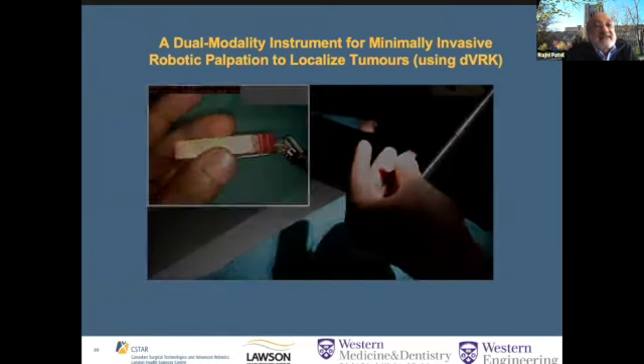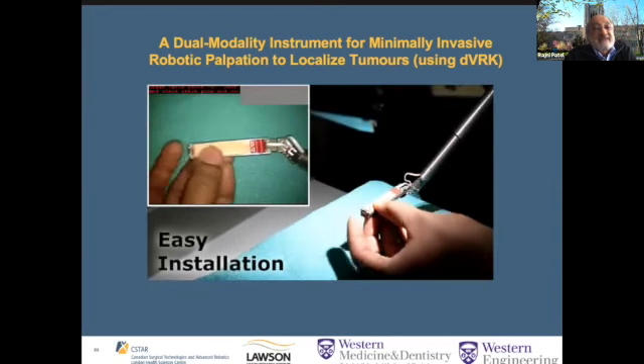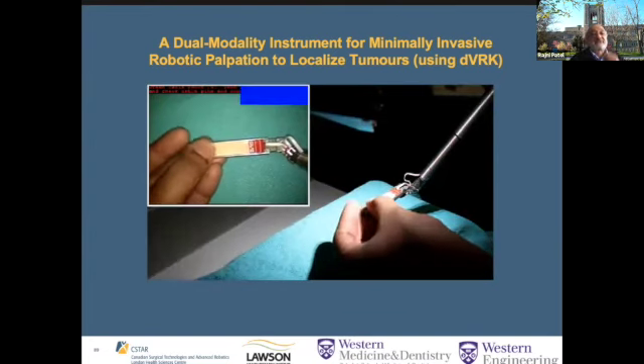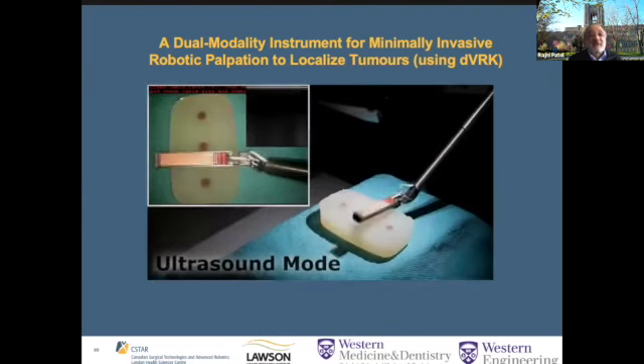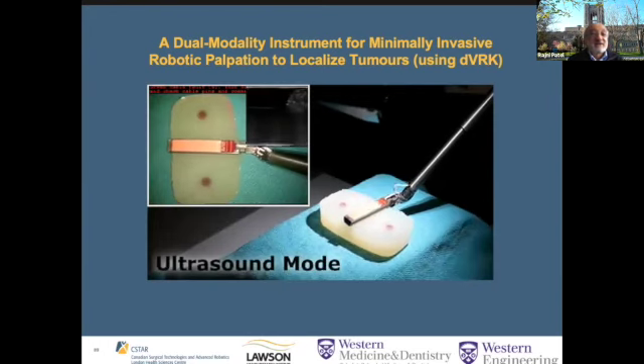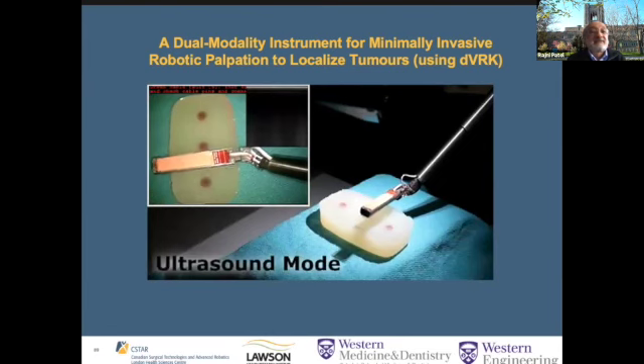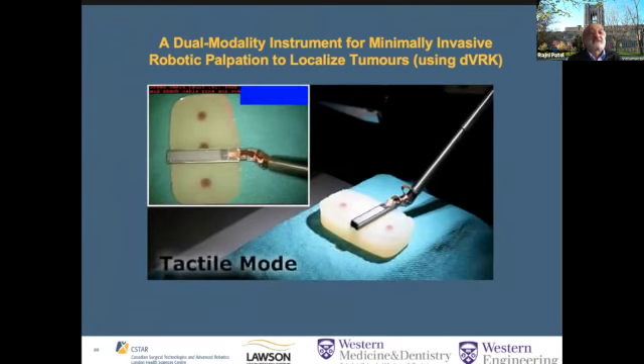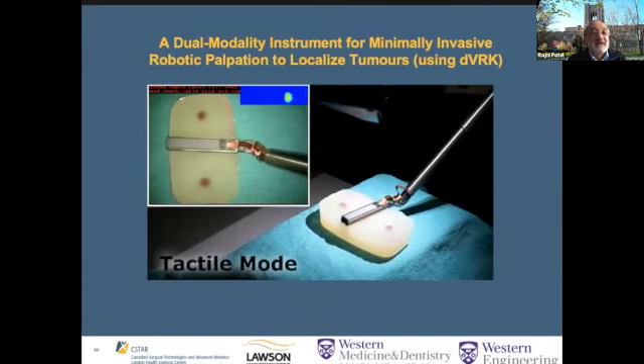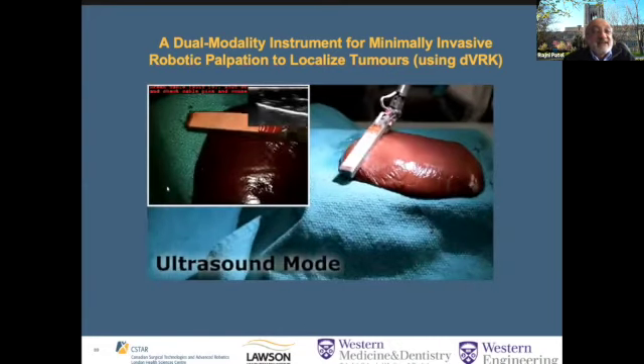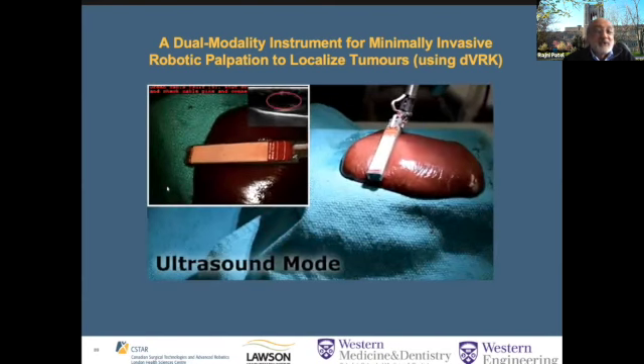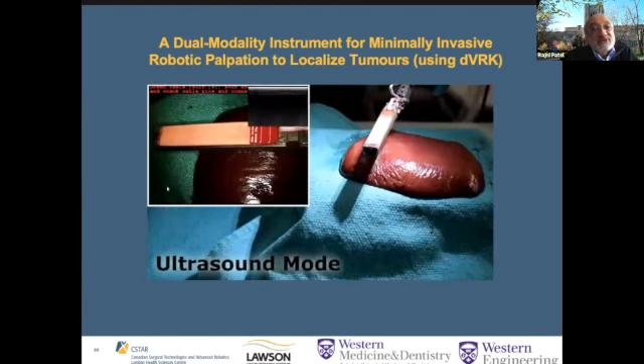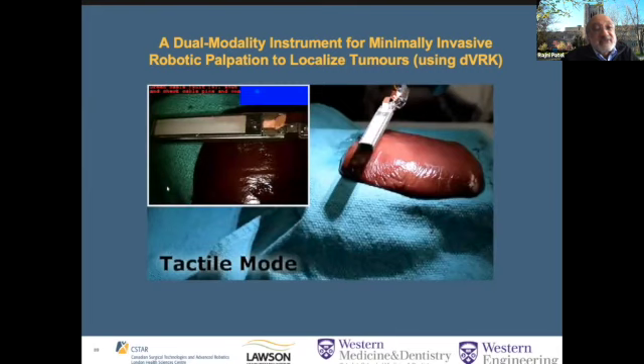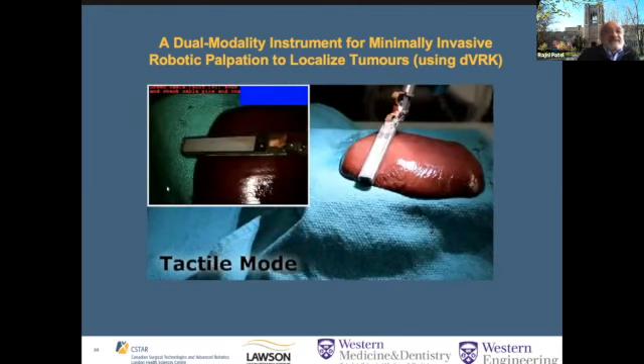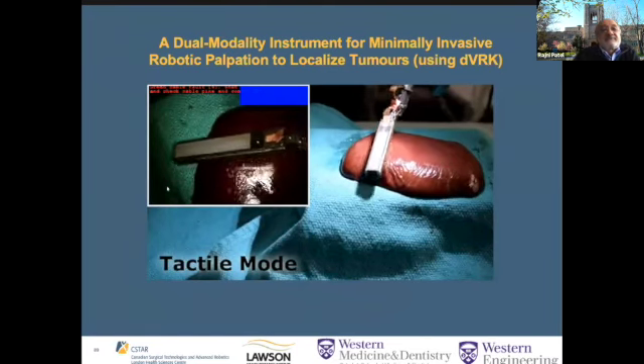So this is the tactile sensor. It can be very easily mounted on the instrument. And on the other side, there is the ultrasound transducer. So when this instrument is inserted into the body, it can palpate tissue, and at the same time, with the same instrument, by simply flipping the instrument around, it can do ultrasound imaging of the tissue. And then the pressure map and the ultrasound image can be integrated to provide a much better view of the tactile sensor. This can also provide depth information of the tumor because of the ultrasound imaging information. Here, the test is being done using a liver sample.